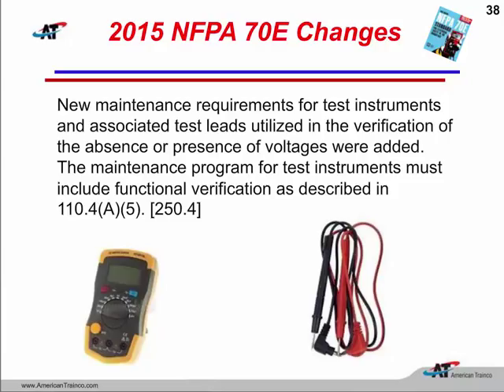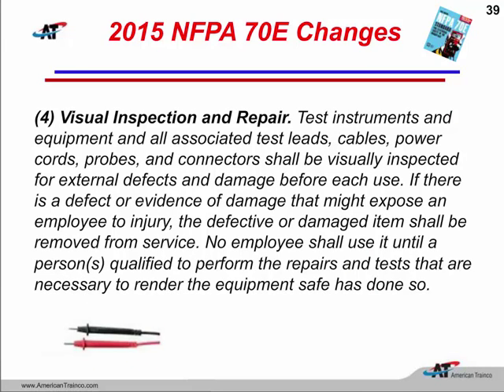And this falls under Chapter 2, which is our maintenance requirements in 70E. It also states that the meter is part of our personal protective equipment. It's the only way we can verify the absence of voltage. So we should be maintaining our meters and test leads in accordance with the manufacturer's instructions. They are also going to tell us that all these leads have to be inspected for any kind of damage before each use. The meter is also going to have to be given a visual inspection.